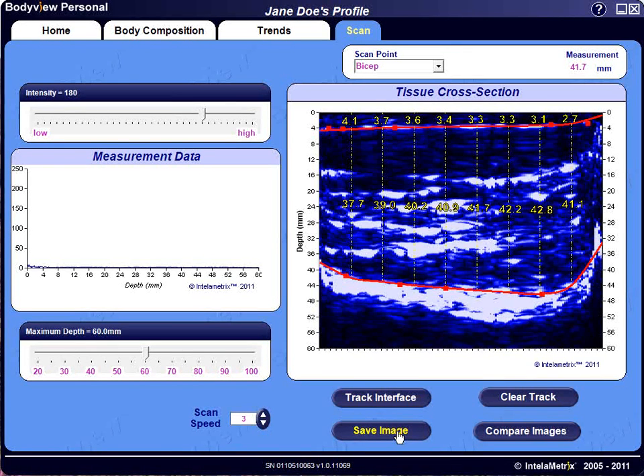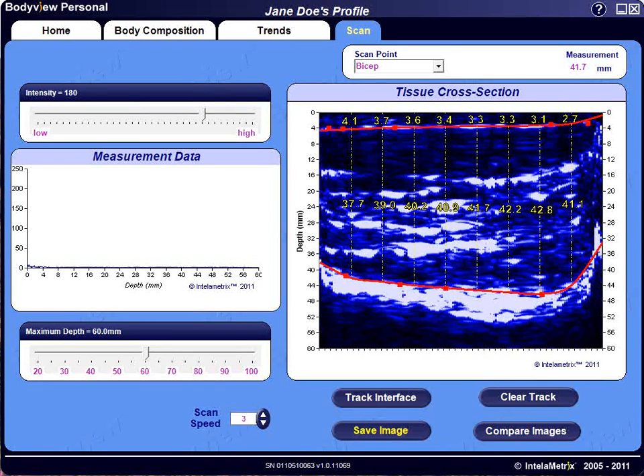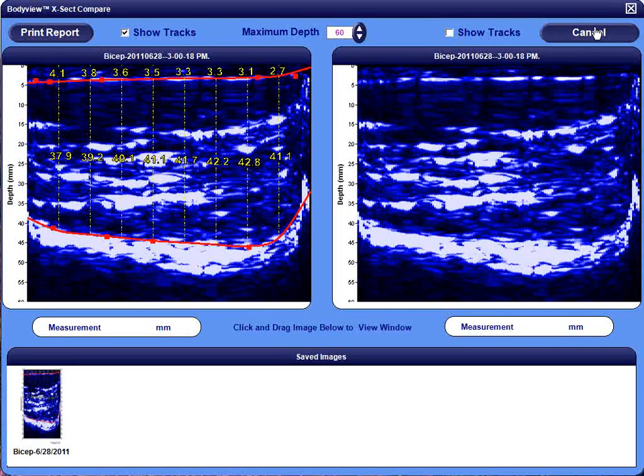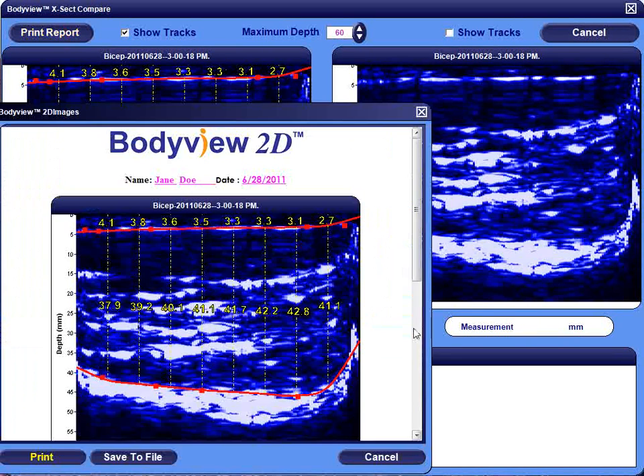When you select Save Image, that scan will be saved to a gallery for later comparison. Each scan is saved with the body part name and date taken. When you select Compare Images, you can drag scans from the saved images to compare. Tracking can be turned on and off by checking or unchecking the Show Track box. The images can be printed or saved to a file on your computer by selecting the Print Report button.